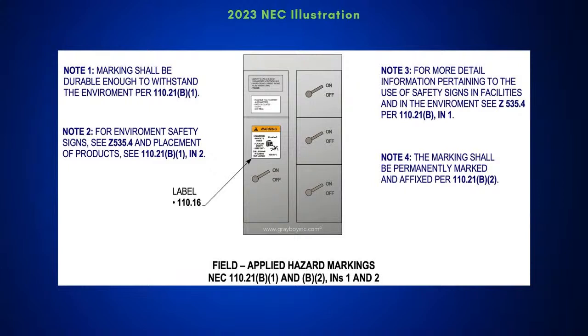Now, that is what you get into when you start looking at this, and you have to know exactly what is required. Here's what you get into when you look at 110.21B, and this is where you get into your labeling. If I put that information on there, that marking has to be permanently marked and affixed per 110.21B2. Now, the labeling on that equipment is a warning. So since it's a warning, that top portion is going to be which color? Orange. Yep. If this was a danger, it'd be red, but we're giving you a warning here.